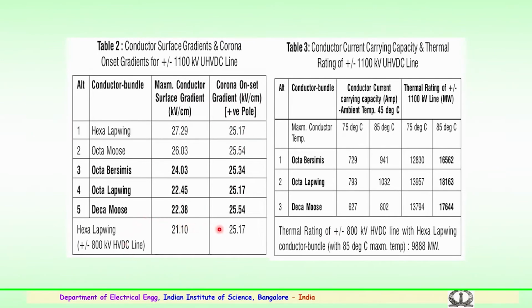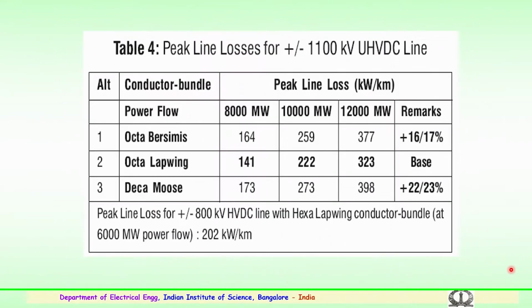A lot of studies are in progress. Similarly, conductor current carrying capability and thermal rating, when you go for 1100 kV, for that power rating you see at the maximum conductor temperature of 75 degrees, in case it goes to 85, 75 and 85, the thermal rating, the various conductors' performance. You can see that for Octa Bersimis these are the values, and lapwing 8 conductor, 10 conductor, these are the values which are being estimated. So, a lot of studies are being carried out to find out the feasibility of going in for a 1100 kV UHVDC line in the country.